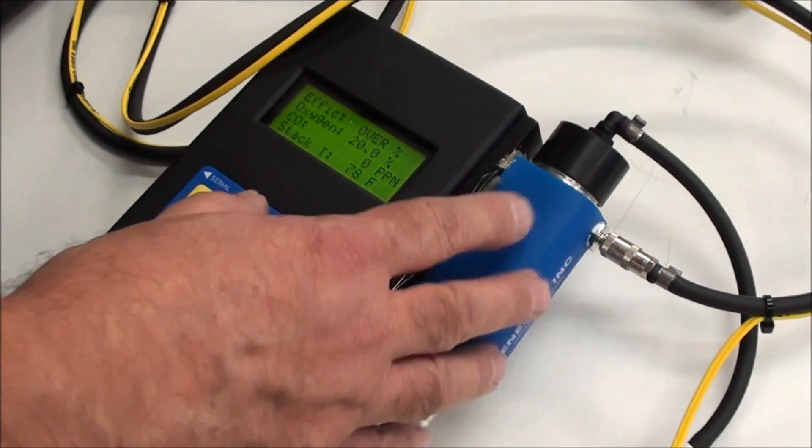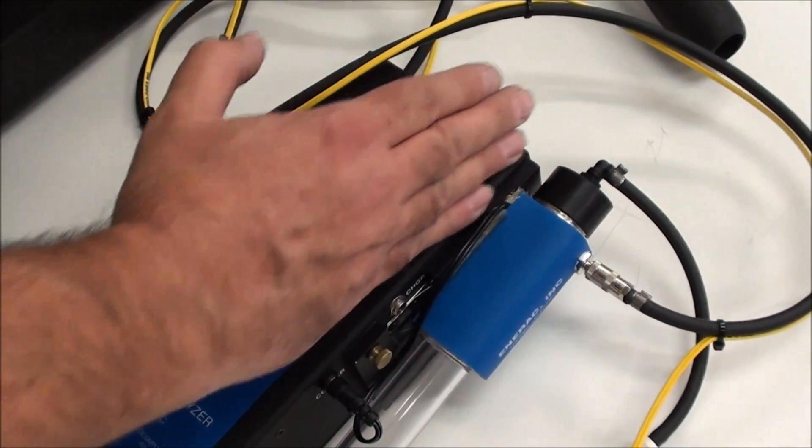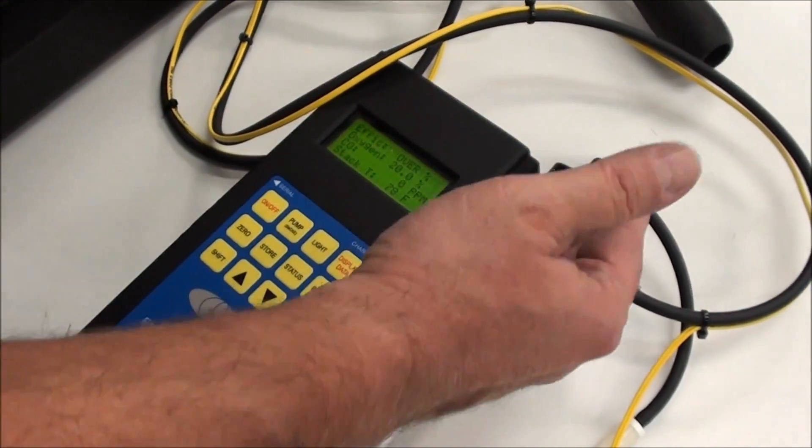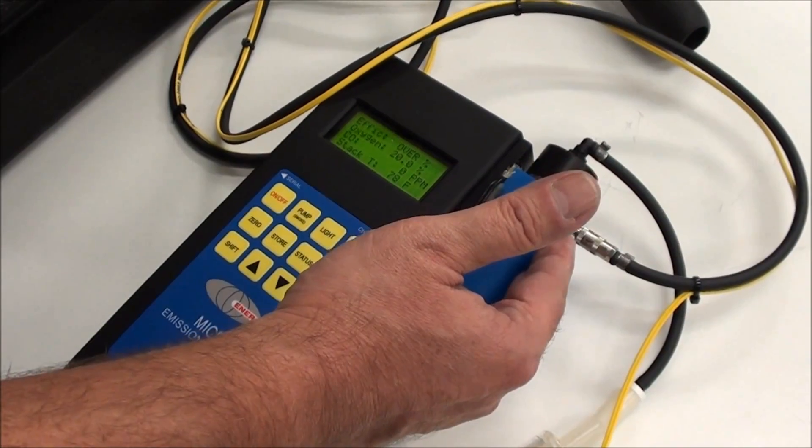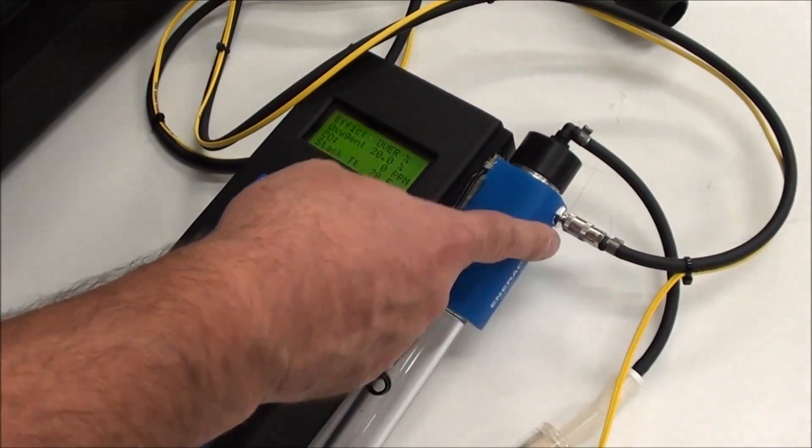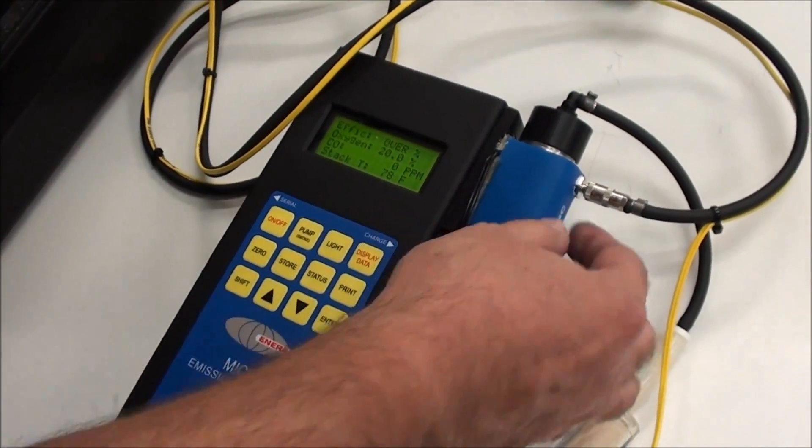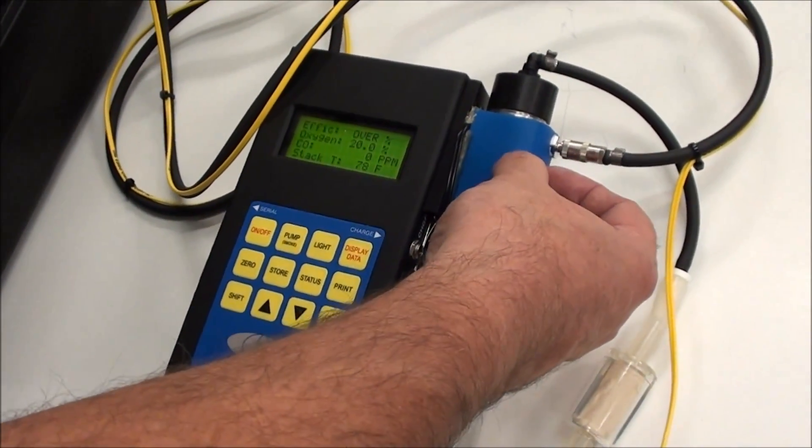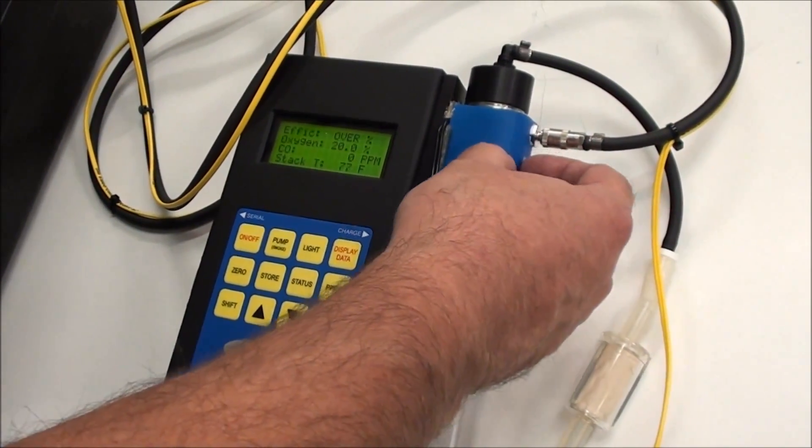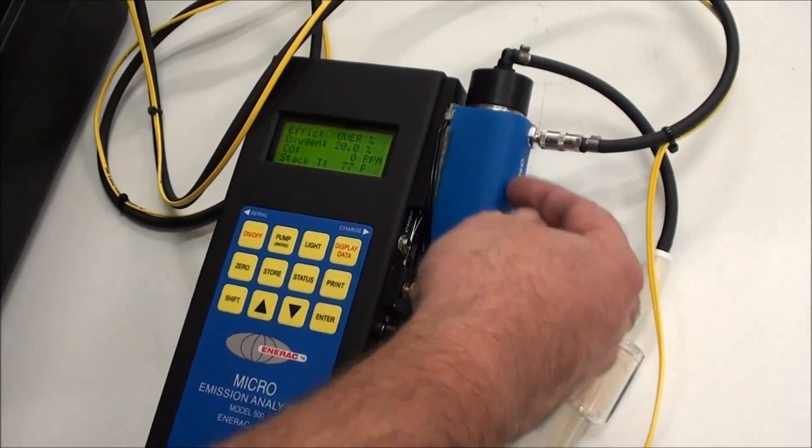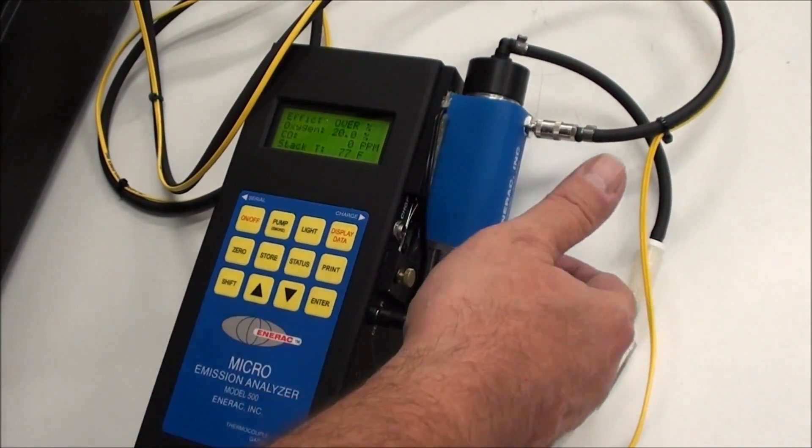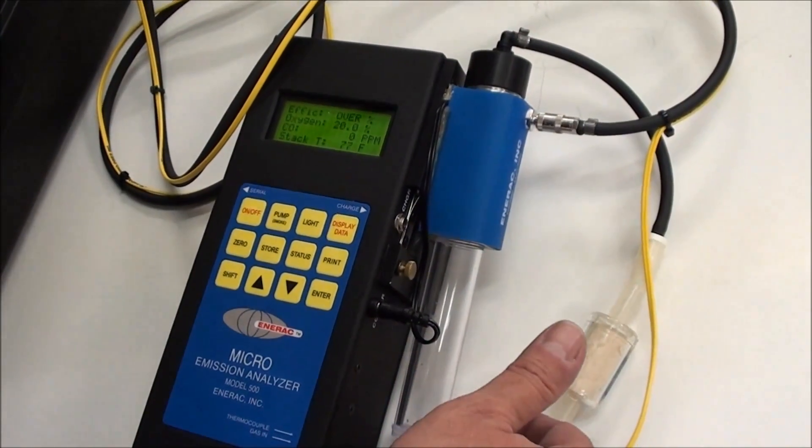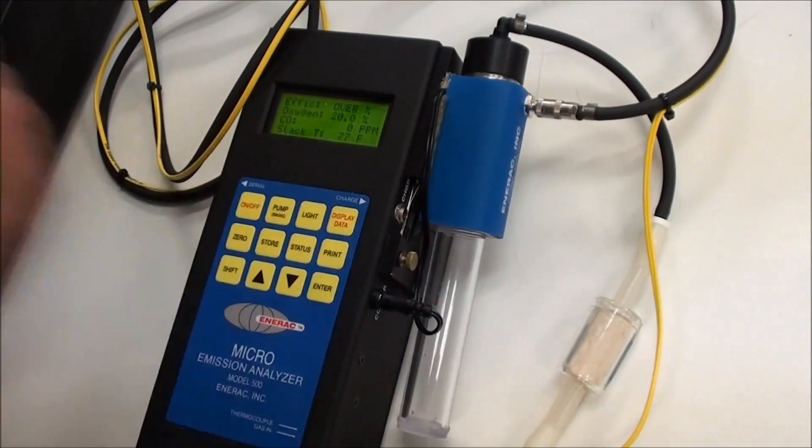The object here, you'll find that one side gets warm. The other side will get cool. What that does is if there's any moisture coming through as a vapor, the intent is to have the moisture condense on the inside of the aluminum block that's under here, and then drop out the moisture, and it'll collect in the bottom if there's a lot of moisture.